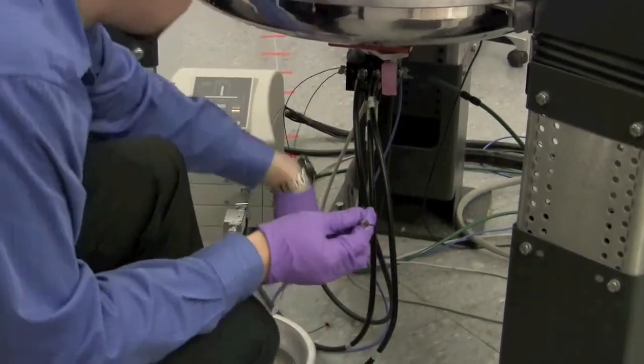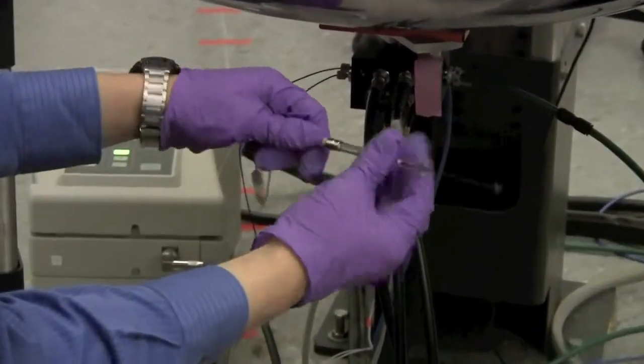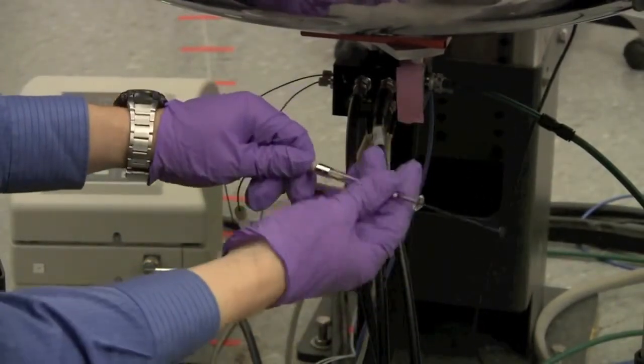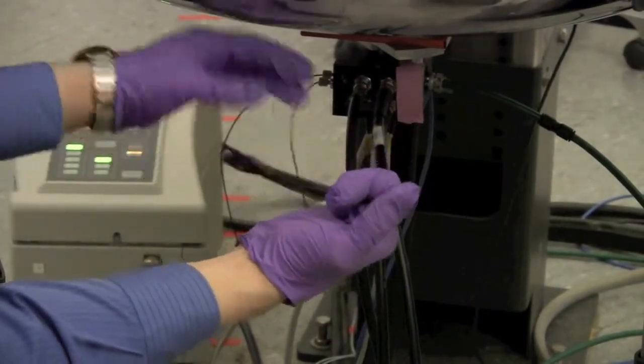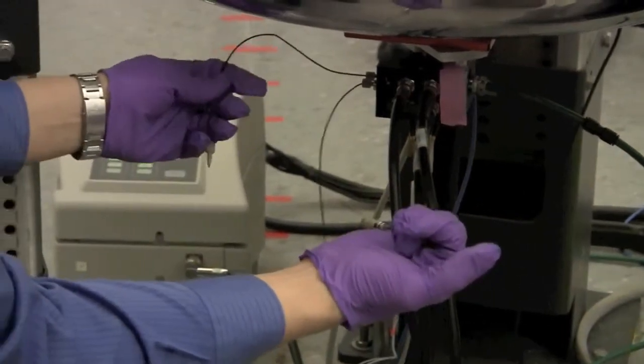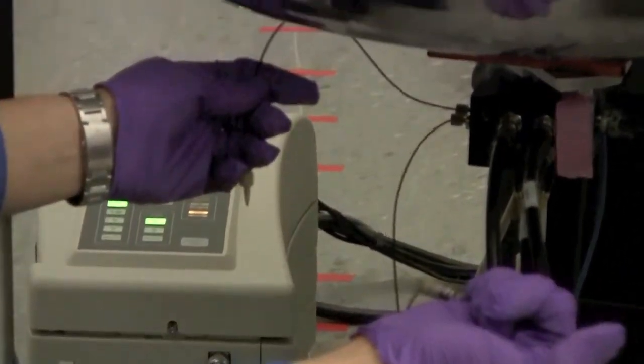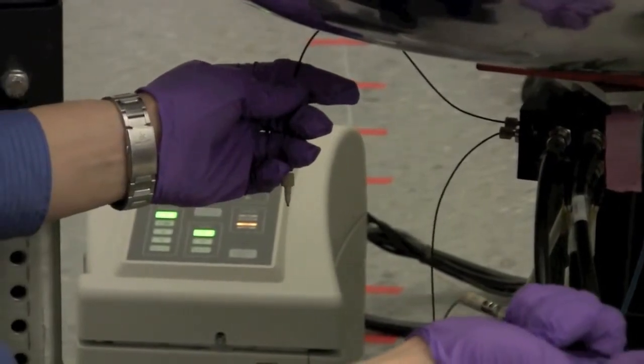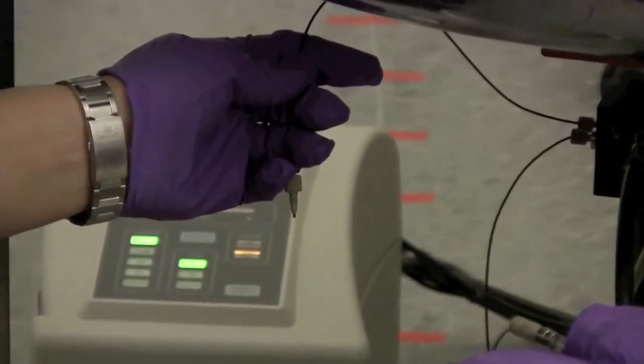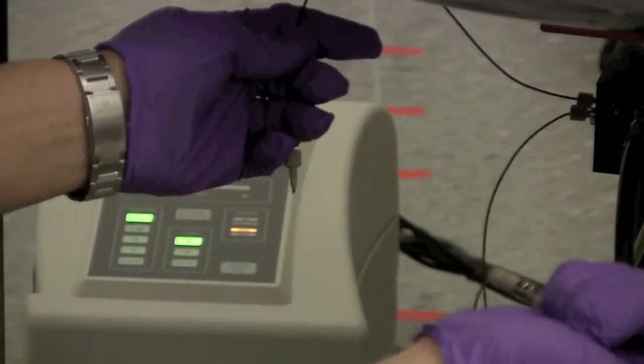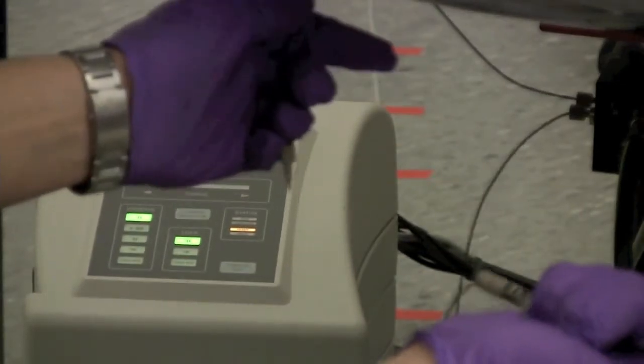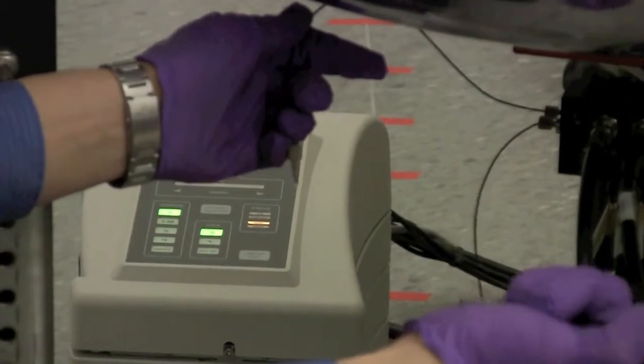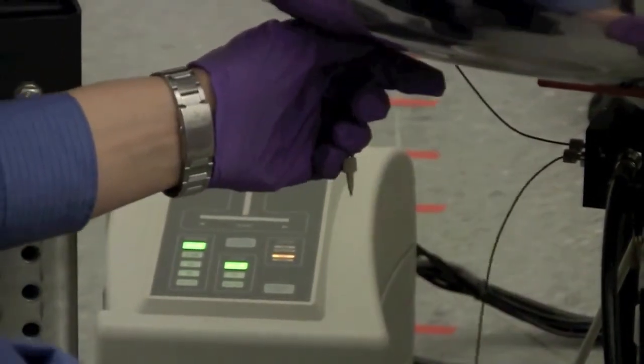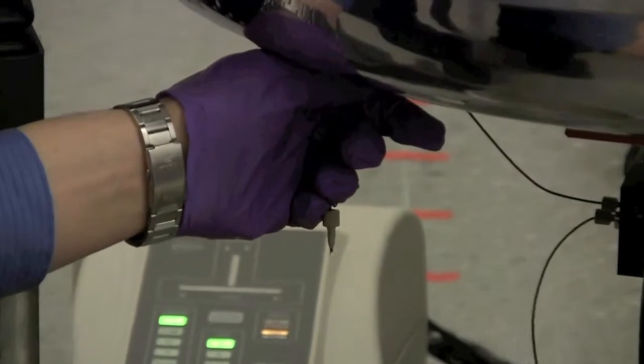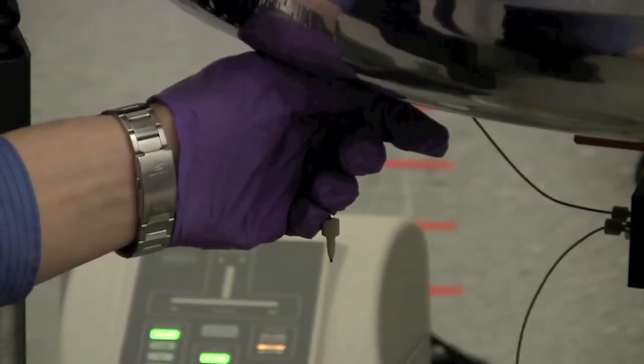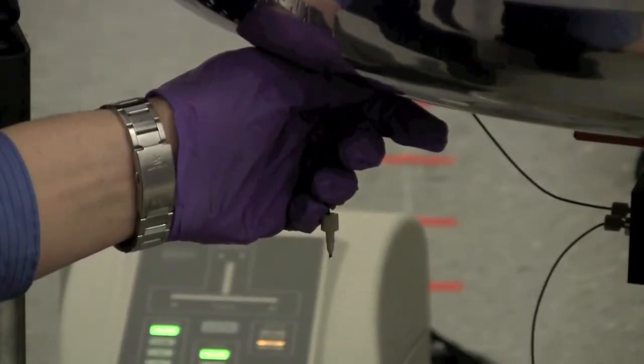So now I'm going to attach this syringe onto the luer lock connection, and I'm going to push the acetone through the probe. Now there may be a fair bit of back pressure as you push it through. That's normal. Just be aware that if you push really hard, you have the ability to create quite a bit of pressure. You have quite a bit of mechanical advantage here. So what you want to do is push it through so that the acetone comes through at a reasonable rate. You don't want to push it so hard that it starts leaking.